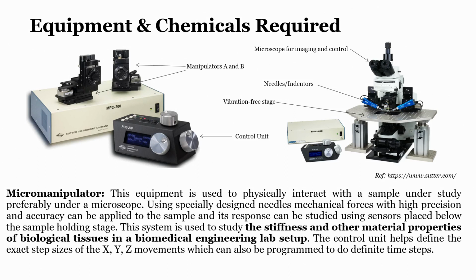This is another very important equipment, and again you will see it as a part of the lab component: the micro-manipulator. So what exactly does micro-manipulator mean? A micro-manipulator is an equipment that is used to physically interact with a sample under study, preferably under the microscope. Using specially designed needles, mechanical forces with high precision and accuracy can be applied to a sample, and its response can be studied using sensors placed below the sample holding stage. The system is used to study the stiffness and the material properties of biological tissue, and it also helps define the exact step sizes of XYZ movements, which can also be programmed to definite time steps. Easy? No, it is confusing, right.